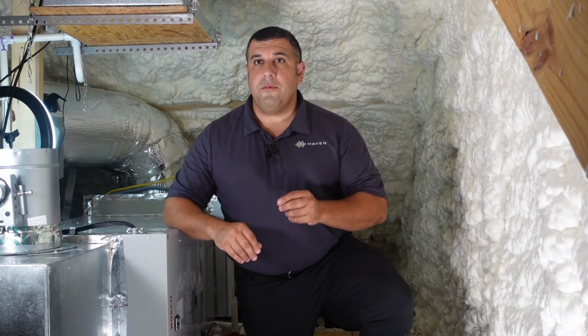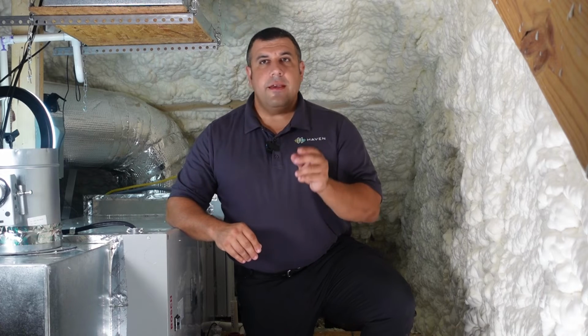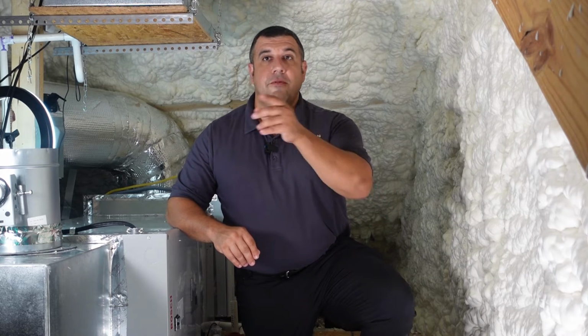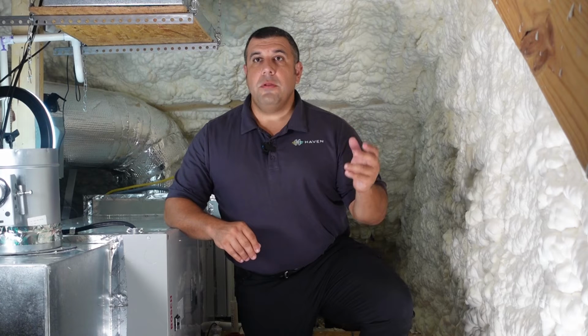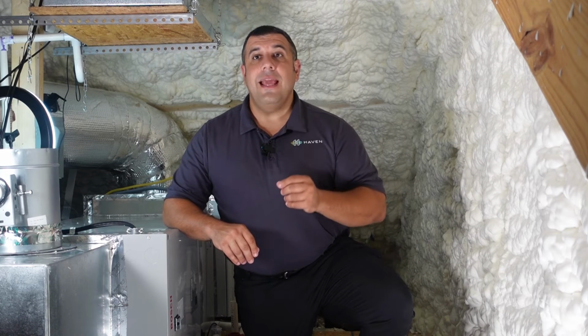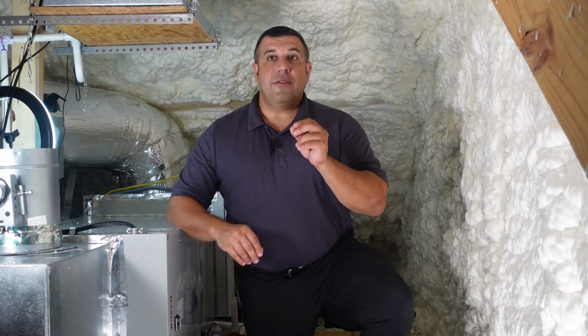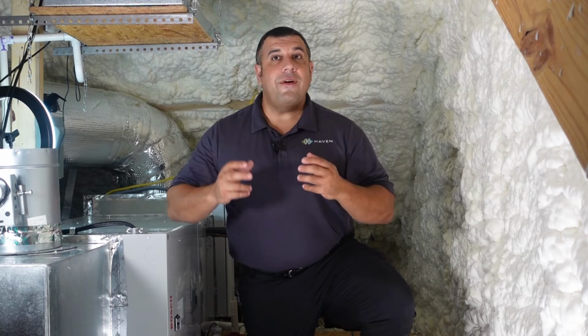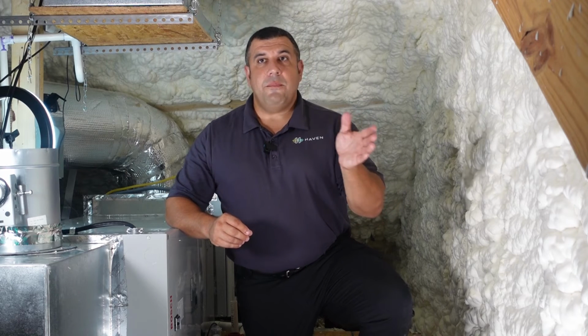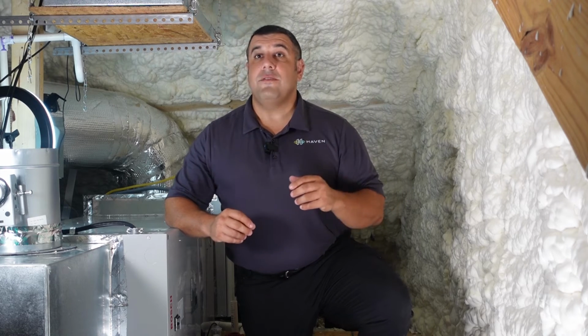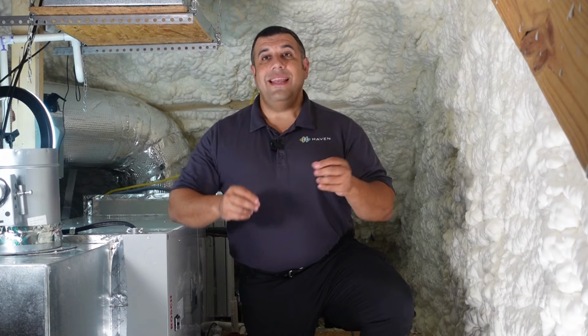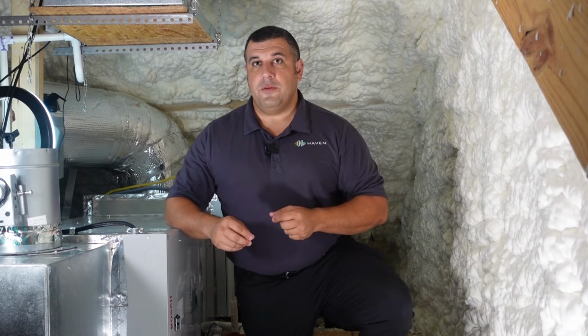Now the monitor will perform a self-assessment test to make sure that it's fully operational before you leave the home. This requires a blower fan to be on and circulating airflow for a few minutes. During this test, the app will ask a few final questions about the install, then provide either a confirmation of the successful installation or confirm what needs to be changed before leaving the customer's home.